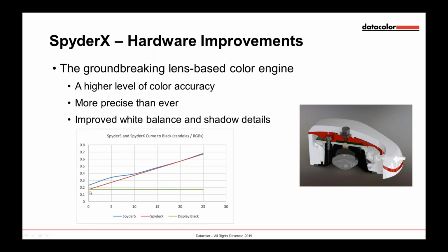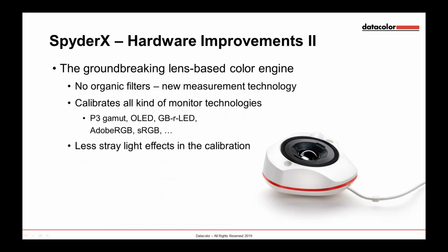So what the software did, it compensates, of course. So there's an algorithm behind it that, let me say, corrects the measurements that can be done with the older technology, but the SpyderX is much more sensitive, and you see it in the graph or on the image on the right side. There's the lens inside, means it really focuses the panel in your monitor, while the Spyder 5 was collecting the light with its honeycomb filter. Yeah. But we will see this in a few seconds a little bit closer.